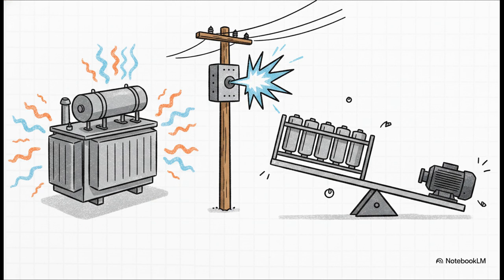So here's the fix. Engineers install huge capacitor banks in parallel with the load. Capacitors supply leading reactive power that literally cancels out the lagging reactive power from heavy motors. The exact formula for the correction capacity you need is QC equals P times the difference between the tangent of your current angle and the tangent of your target angle. Add exactly that many kVAR of capacitance, and you shrink that triangle's height, dropping your reactive draw without touching real power. It's a multi-million-dollar trigonometric fix.